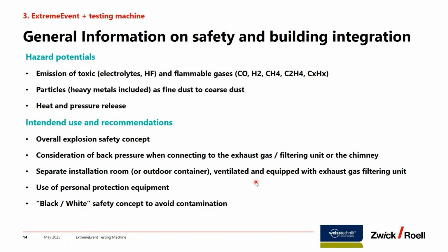If you have an event with an explosion, then most of the gas and all the parts are inside the extreme event chamber and not spreading in the room. Of course, we anyways need this separated area because even when you start opening the door, you are contaminating this room.